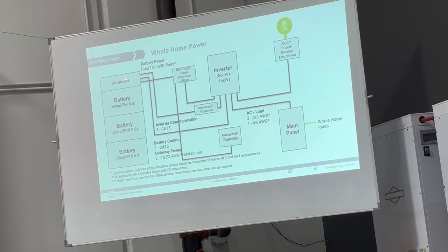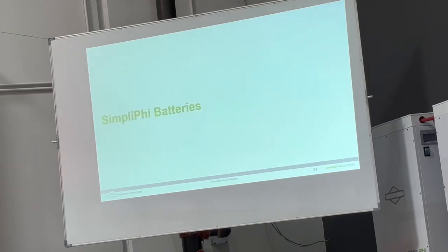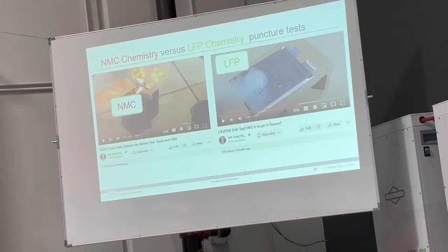And then the communications out of the controller, we have two communications lines. A communication line going to the gateway, and then a communication line going to the Sol-Ark inverter through a dongle. I'll show you in more detail the communications wiring. This was more for the sizing. So we talked about this battery already. I do want to highlight, I mentioned earlier about how NMC chemistry, that's nickel, manganese, cobalt oxide, that NMC chemistry is typically used in batteries that need to be very lightweight.